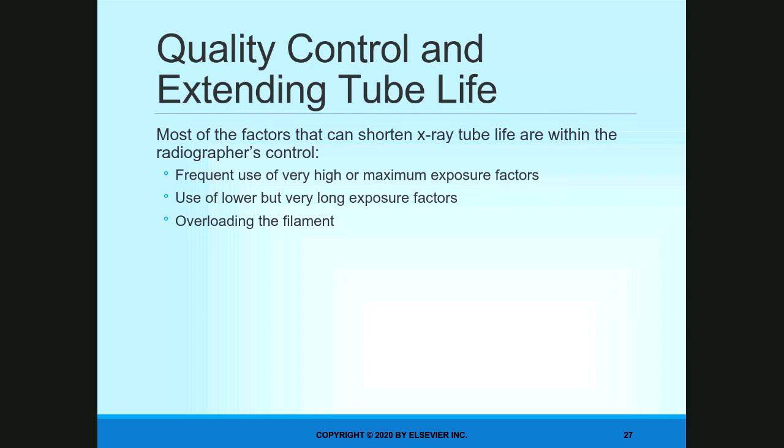We had one tube at Advent Waterman that opened up. When they first opened, their tube in the ER didn't even last a year. It was so overworked and overused that it barely lasted 1 year, and that tube cost well over $250,000. So you really want to make sure as a technologist you're preserving the tube as best you can to give it the longest tube life possible.